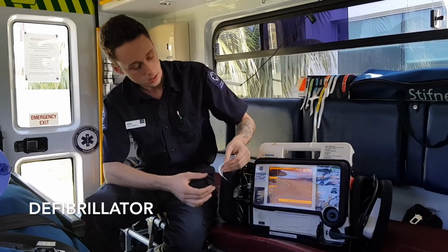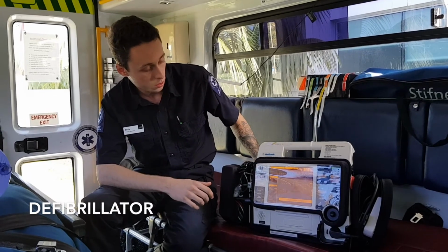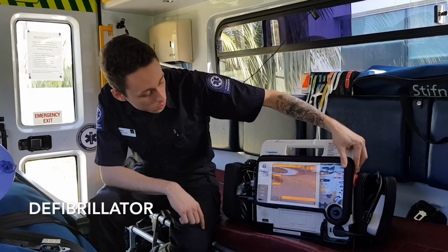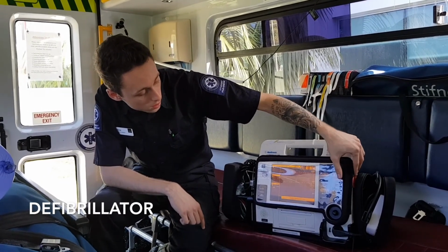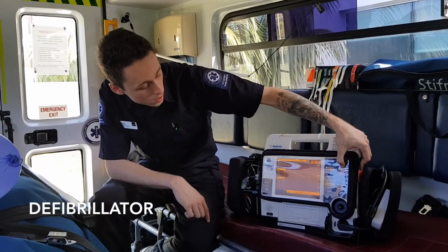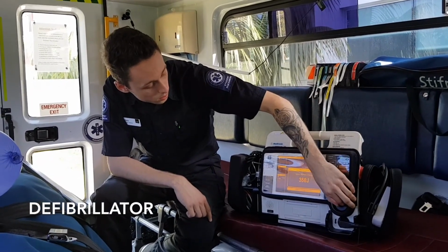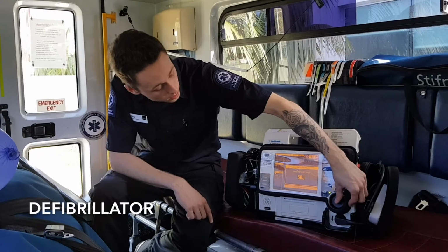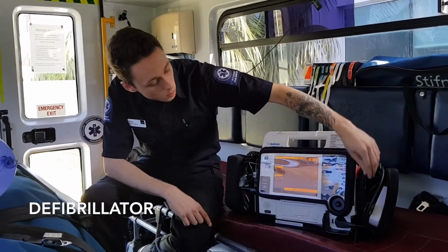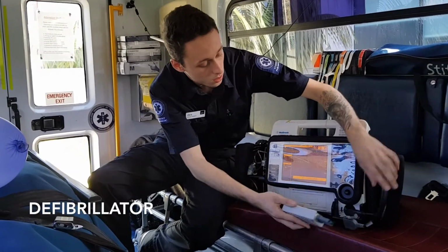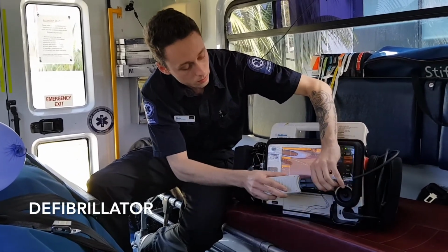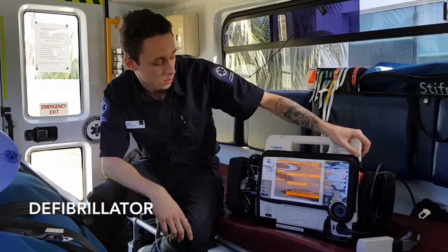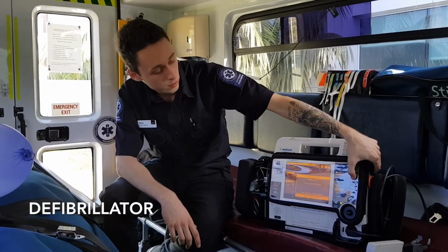Okay, so the operational test has said it has passed, so it's all good to use. And I want to do a defibrillation test. So I will choose the amount of joules we want to use. I'll go all the way down to 50 for this test. Select that. I'll make sure that the test load is attached. I'll begin charging, using the charge button here. I'll wait for the noise and press shock.